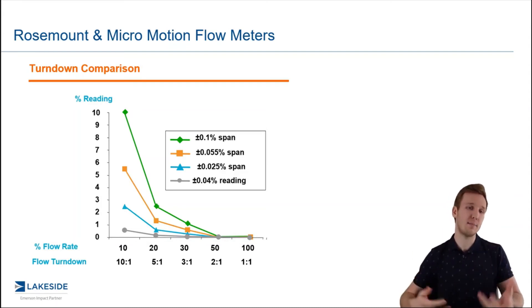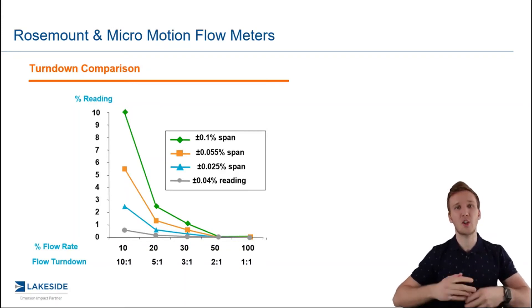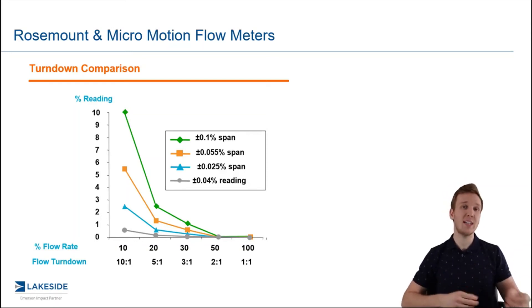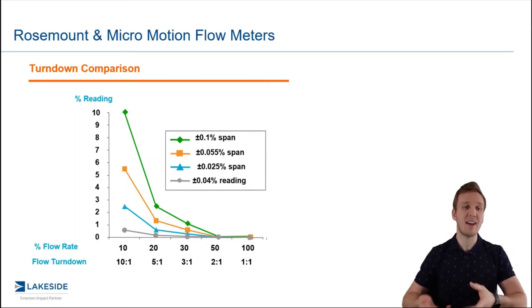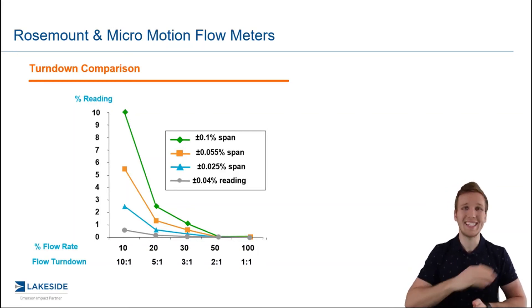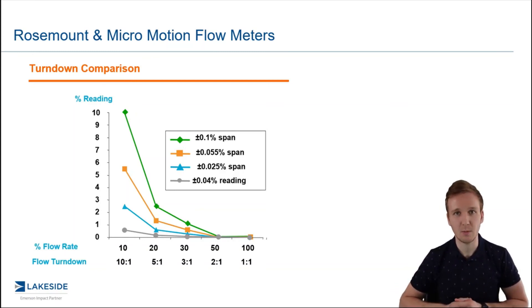The green, orange, and blue lines represent percentage of span, ranging from 0.025% up to 0.1%, and you can see the impact depending on the turndown. At a 10-to-1 ratio — the greatest turndown — we have the greatest error for any percentage of span. The gray line represents percentage of reading, and you can see a much lower error because it stays consistent across the entire flow range. Once we get into those higher turndowns, other factors begin impacting the measurement.